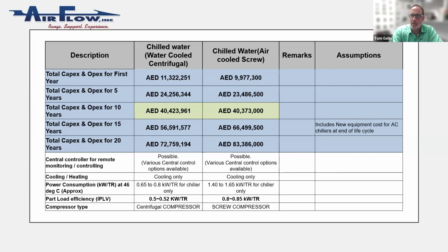So even at half the operating cost, you're basically at a dead heat until you replace the air-cooled chillers with new ones. You get two runs out of the water-cooled versus one out of the air-cooled. I don't know if you replace a cooling tower too, but it's surprising when you look at all of it. I could get cases for both, right? Yep, fair enough. Thank you for that analysis.